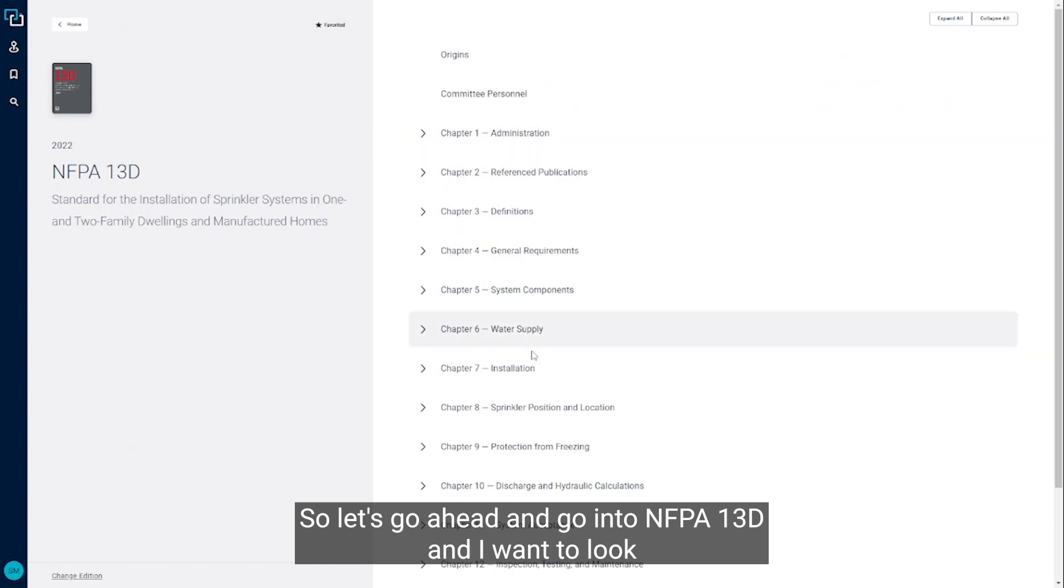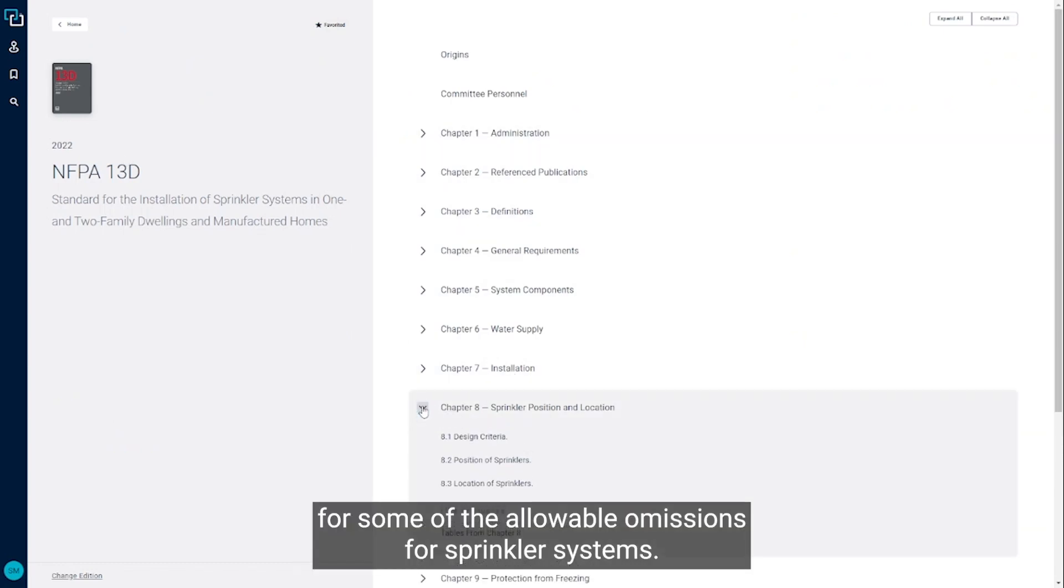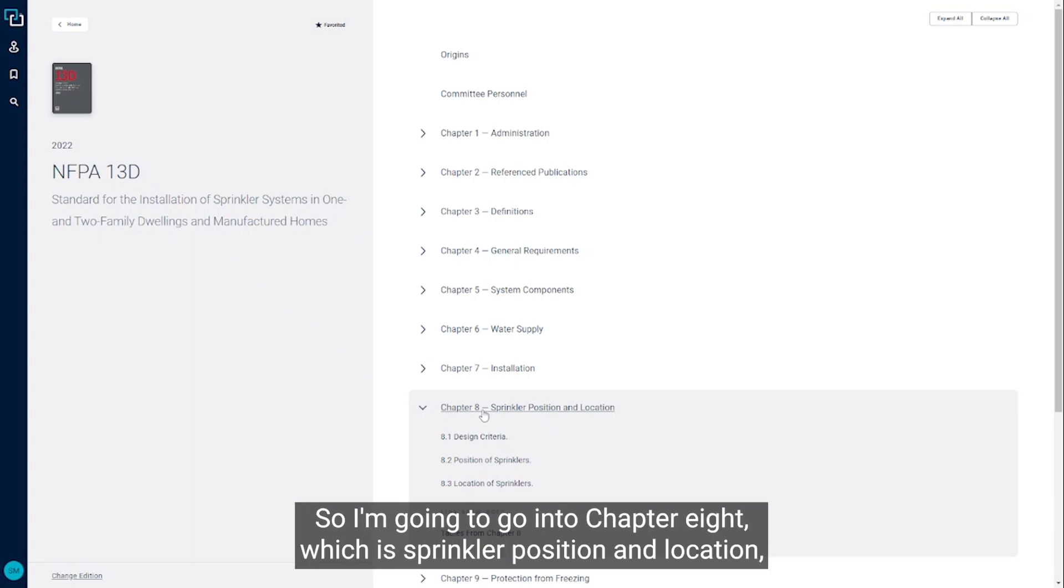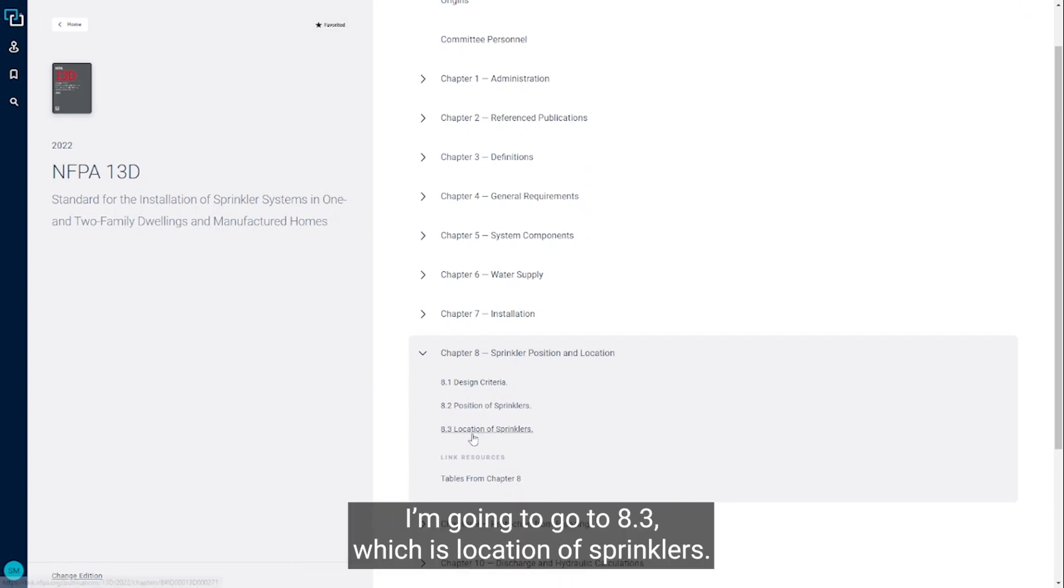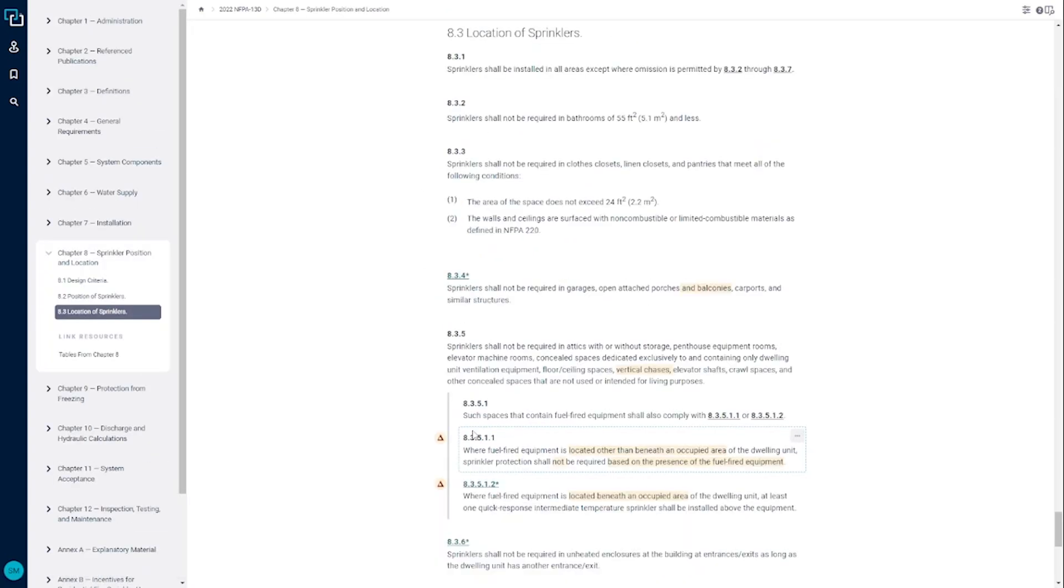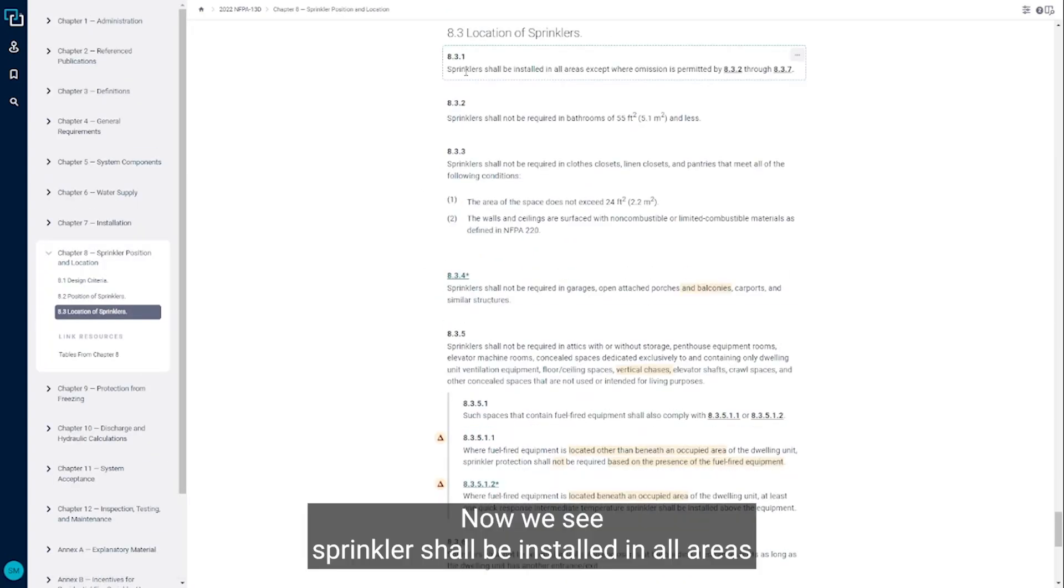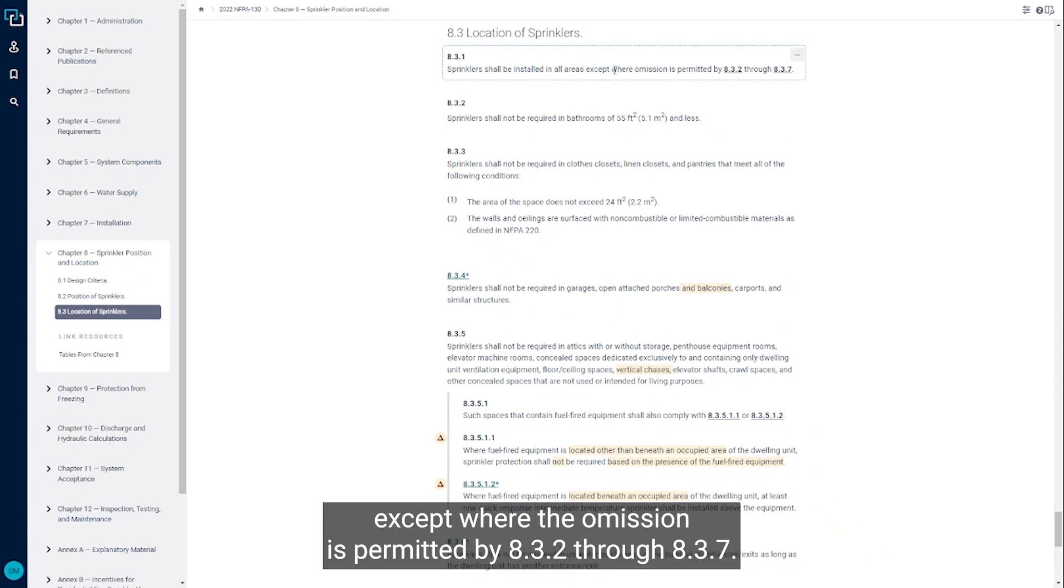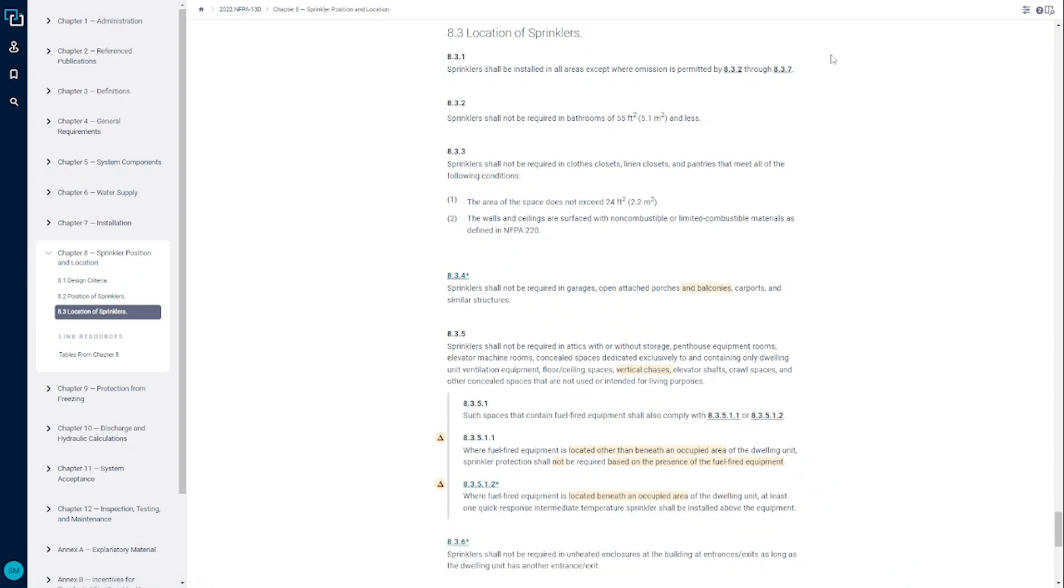I want to look for some of the allowable omissions for sprinkler systems. So I'm going to go into chapter 8, which is sprinkler position and location. And we go to 8.3, which is location of sprinklers. Sprinklers shall be installed in all areas except where the omission is permitted by 8.3.2 through 8.3.7.